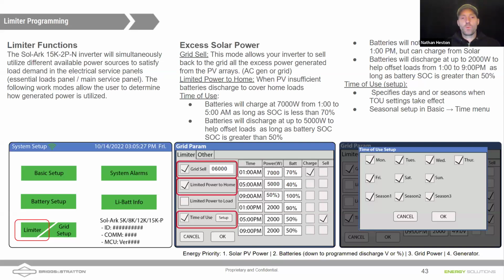Limited power to the load will limit how much overall power you're using from utility to go to your load by supplementing that with battery or solar power, right? So solar power will always be used to try to cover your loads. You can supplement battery power to cover your loads, so you're never pulling more than a certain amount from utility. And that can be very useful for things like peak shaving, right? Limiting power to home, you could shave off peaks from the utility if you're getting charges by going over a certain power threshold. And then, of course, we have the time of use settings.